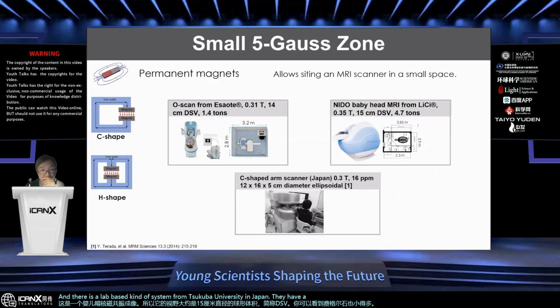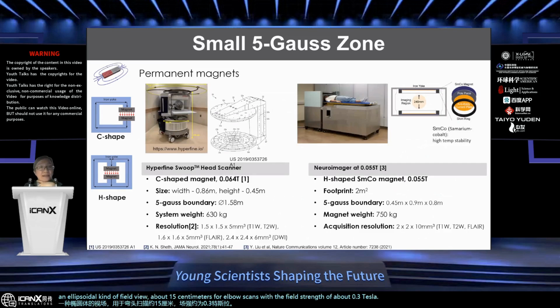They have a system with an ellipsoidal field of view of about 15 centimeters as well, for elbow scans, with a field strength of about 0.3 Tesla. And recently, for the C-shape and H-shape, that is the portable head MRI from a company called Hyperfine. For a system like that, the field strength is about 64 millitesla, and the 5 Gauss zone has a diameter of 1.6 meters, and the weight is more than 500 kilograms.